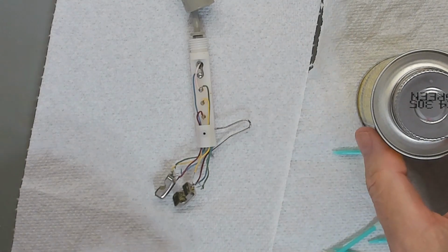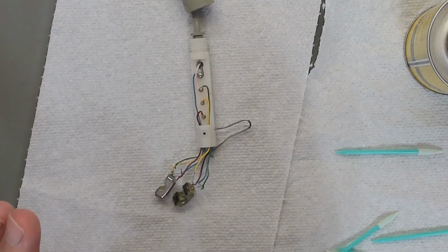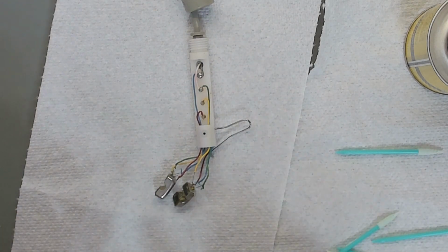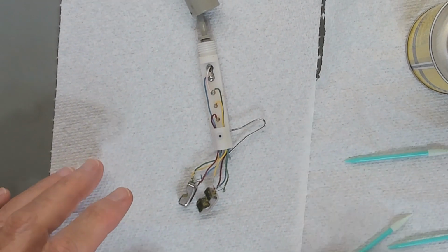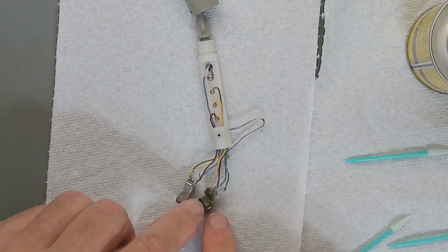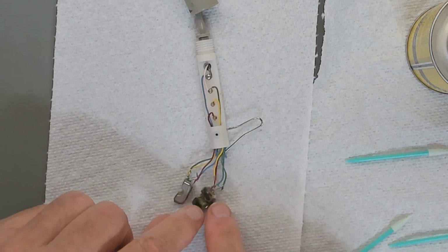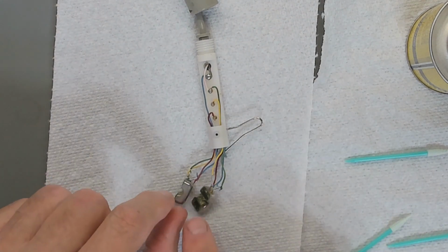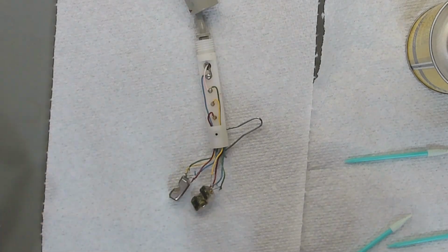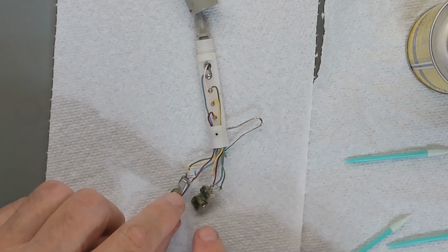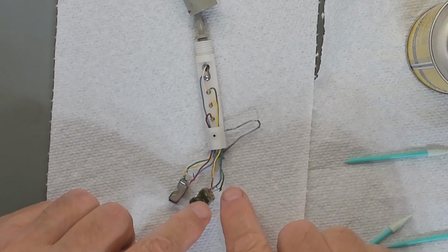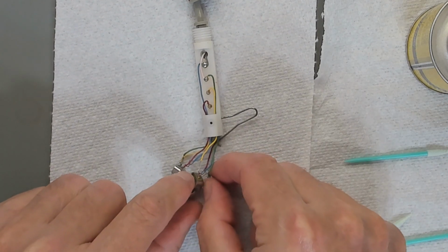So I went online and I looked up disassembling. I disassembled it, and I got in there, and what I found was the probe was stuck together hard. I mean, I couldn't get it apart. I put a screwdriver in there, could not open it. And also the wires here, it's like the insulation melted off.